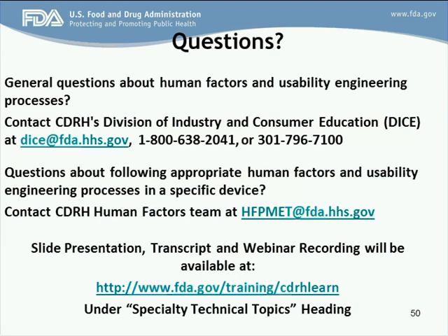This is Shannon Host. I just wanted to add one thing. As you're looking at our requested outline for the human factors report, a majority of that outline is created through the product development process. The majority of that outline, sections 2 through 7, I believe, is the background information that goes into that summative validation report and summative validation testing. And so that is all information that is developed iteratively throughout the development process. And then it culminates, just like your design validation will culminate your design product, in the final validation.